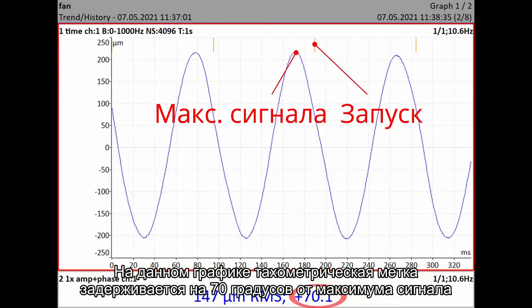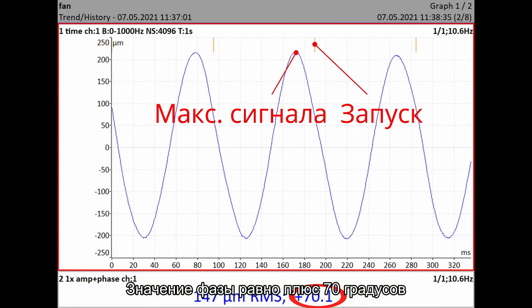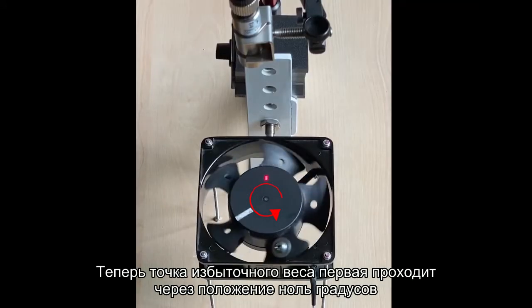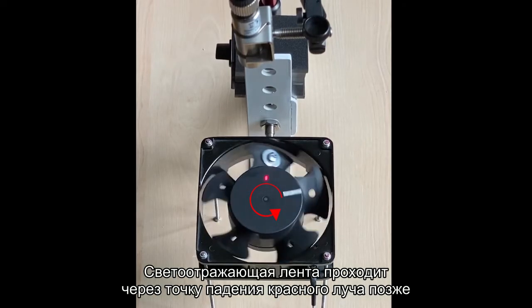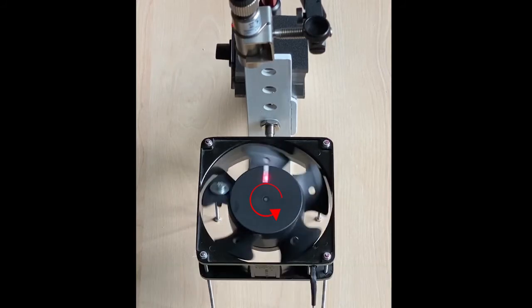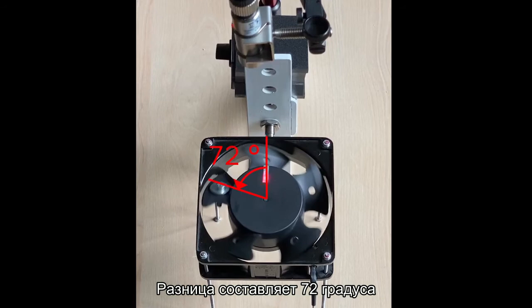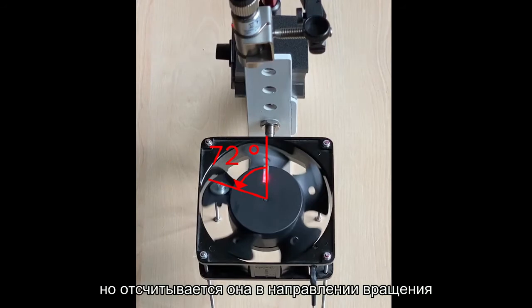In this graph the tacho mark is delayed by 70 degrees from signal maximum. The phase value is plus 70 degrees. Now the heavy spot is going through the 0 degrees position firstly. The reflective tape goes through the red ray point later. The difference is 72 degrees, but it is in the rotation direction.